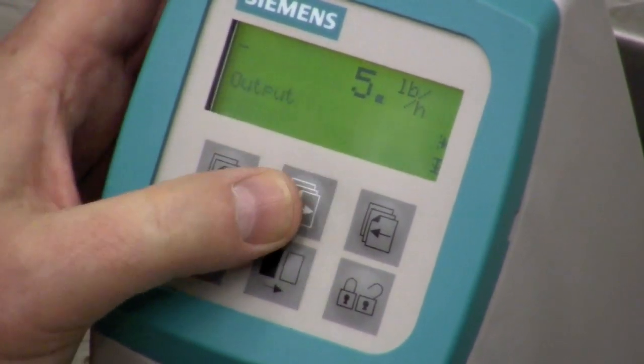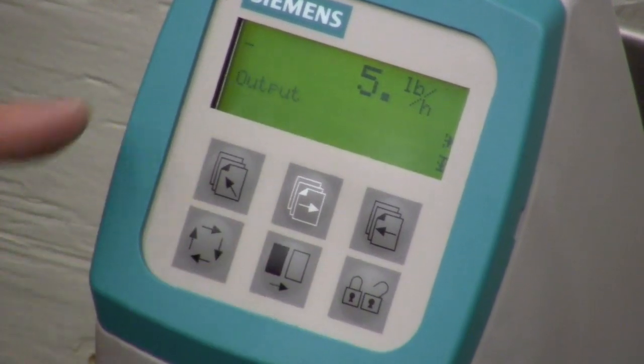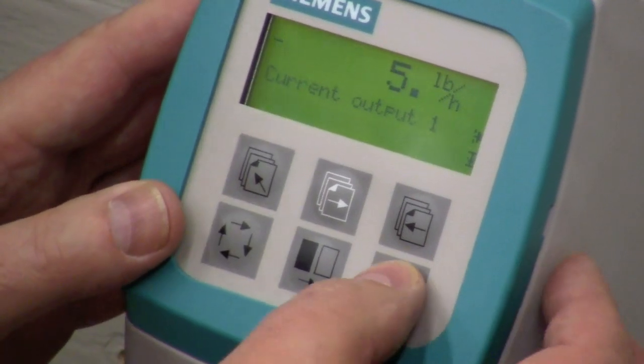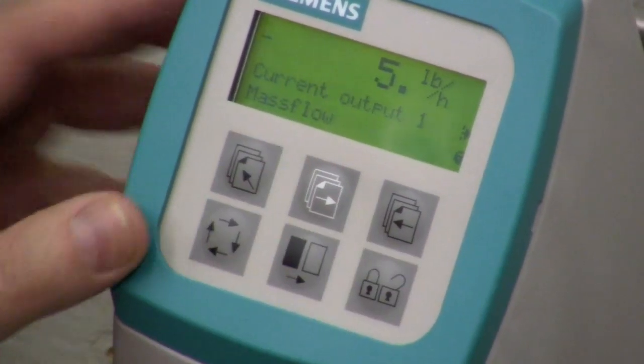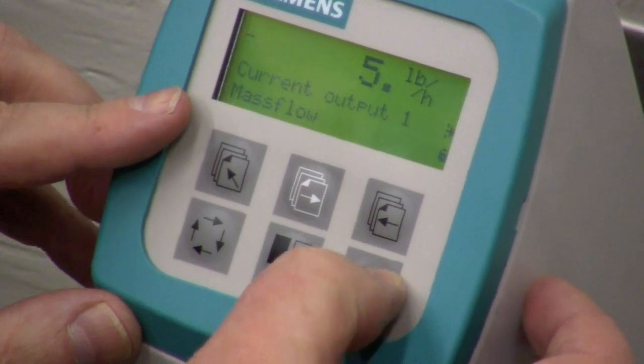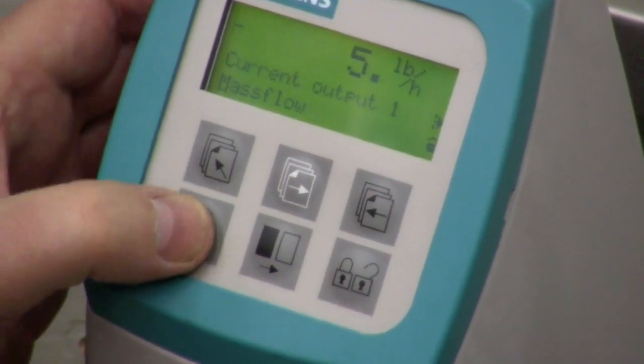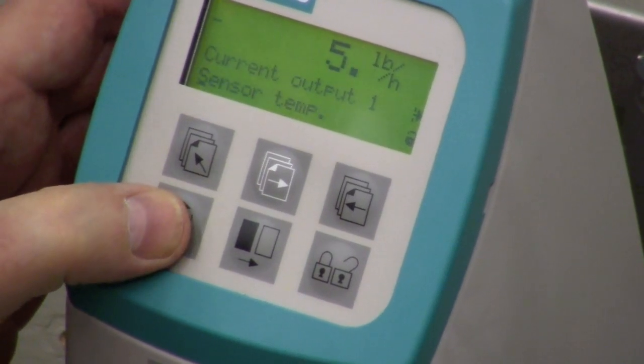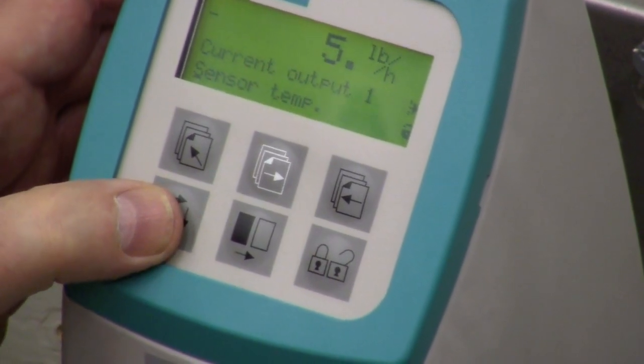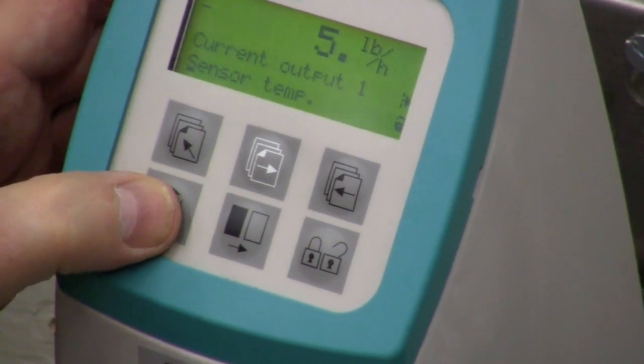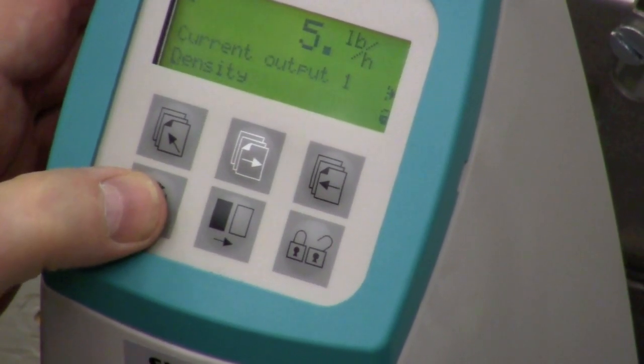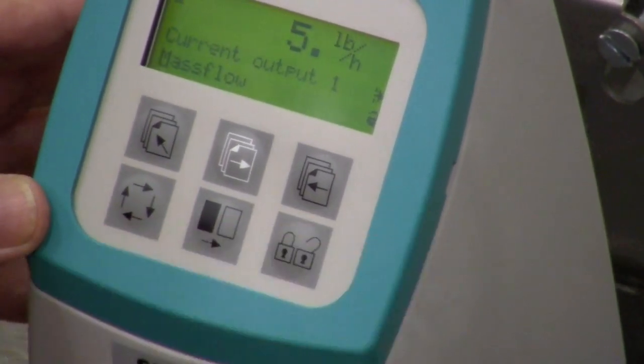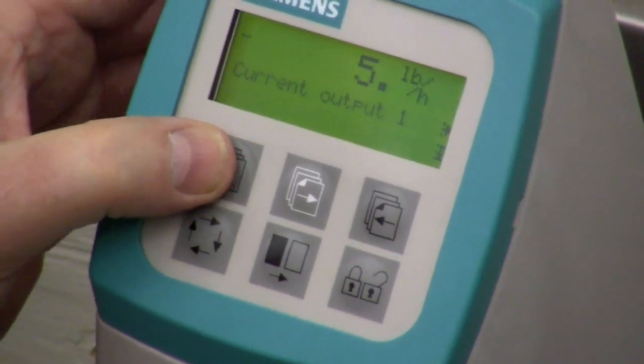Once you're done with your basic settings, you set up your output — that's the next item over. Unlock. Now you set up current output one. For instance, our current output is set up for mass flow. If we wanted to change that, we'd unlock it and use the select button. We can change it to fraction, volume flow, sensor temperature, or density as our 4 to 20 milliamp analog output. But we're going to set it up for mass flow.